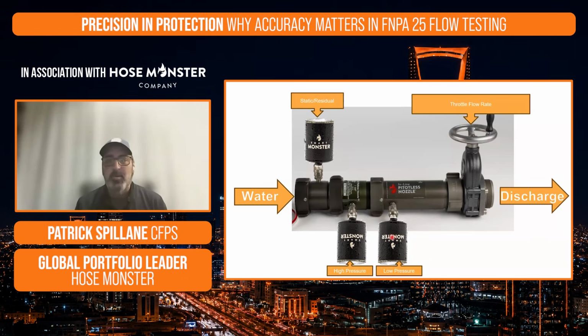We set it all up in our mobile app, right? And now we have our flow rate designed right there in our app. And then our gate valve here is going to connect to our discharge hose, and then we can discharge that water to wherever it needs to go, whether it's up outside the building, up to the rooftop, or to an express drain if there is one in the stairwell.